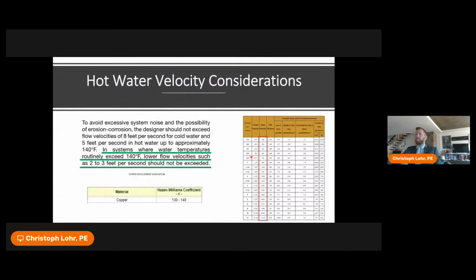All right. Another one of the variables we have to be mindful of is velocity limitations. Again, remembering velocity was one of those 4 equations that I had indicated. For copper piping, per the Copper Development Association, for hot water systems up to 140 degrees Fahrenheit, 5 feet per second is the maximum velocity. In systems where you exceed 140, which is happening more and more often because of Legionella concerns, many systems now are being designed for 160 degree distribution in the mains and main branches. You have to slow that velocity down to 2 to 3 feet per second. Again, otherwise you have an increase in erosion corrosion concerns of the piping material.